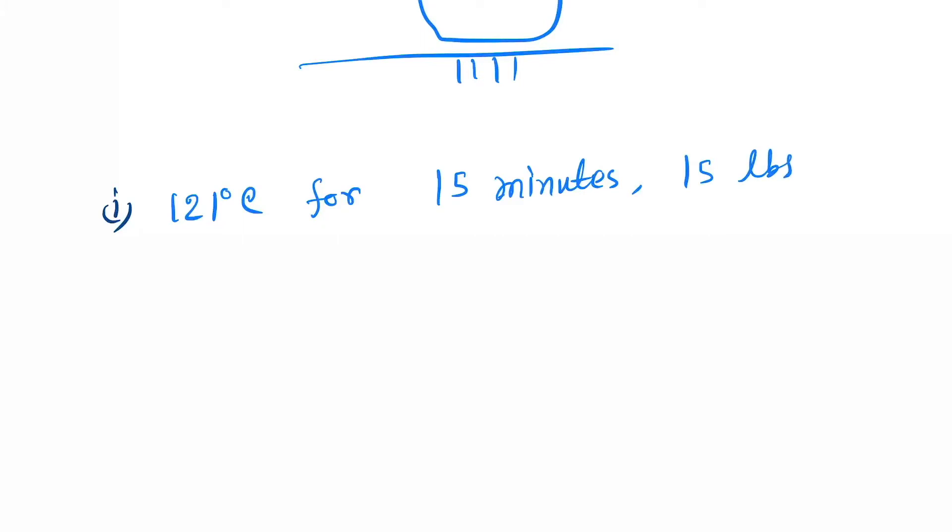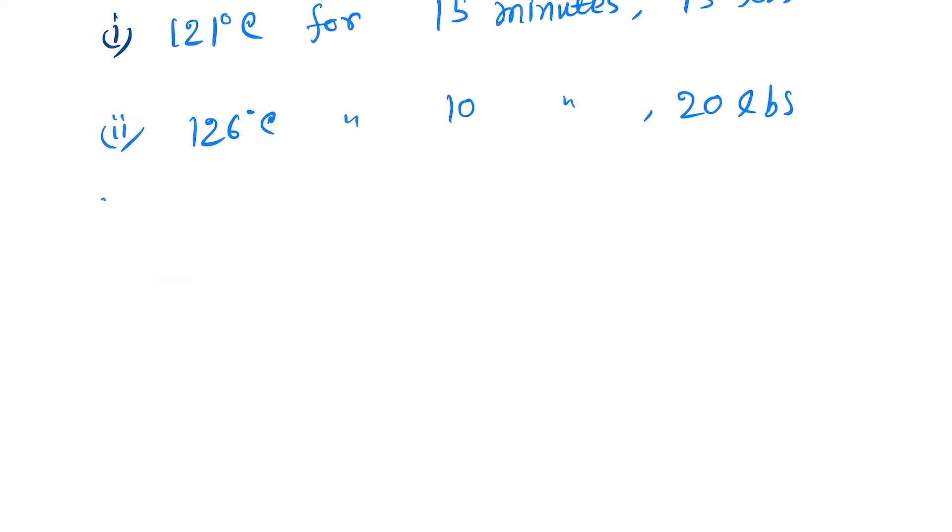Next is 126 degrees Celsius for 10 minutes, pressure will be 20 lbs. Next is 133 degrees Celsius for 3 minutes and the pressure will be 30 lbs.